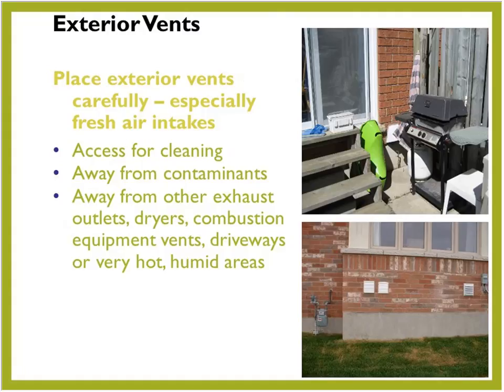If you've got HRVs and ERVs, you want to be careful where you put those intakes, because if it's Sunday afternoon and the Detroit Lions are playing the Green Bay Packers, and you see next to that green, I'm not sure what the green thing is in that top picture, but next to that, behind the grill, is an intake for an HRV or an ERV. Well, if you're grilling brats and sauerkraut on Sunday afternoon, and that intake is sucking the air into the building, your whole house is going to smell like brats and sauerkraut. That may not be a bad thing, but you just want to be conscious of where you're putting it. You don't want to build a dog coop around your intake for your HRV or ERV, certainly. And we also want to make sure that they're spaced far enough apart. Like in the bottom picture there, you'll see on the left there's 2 exhausts, and on the far right a fixed grilled intake. We want to make sure that we're not getting cross-contamination.